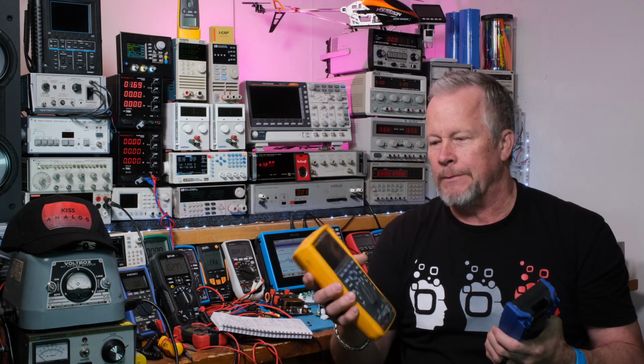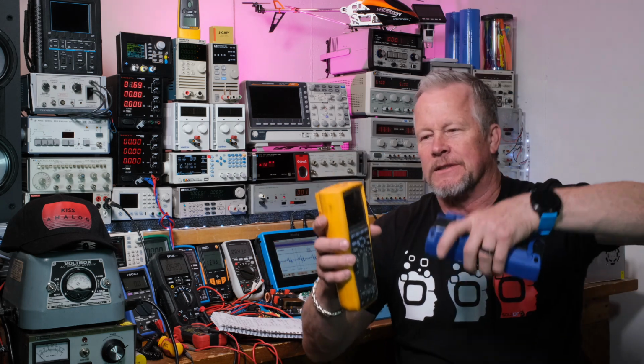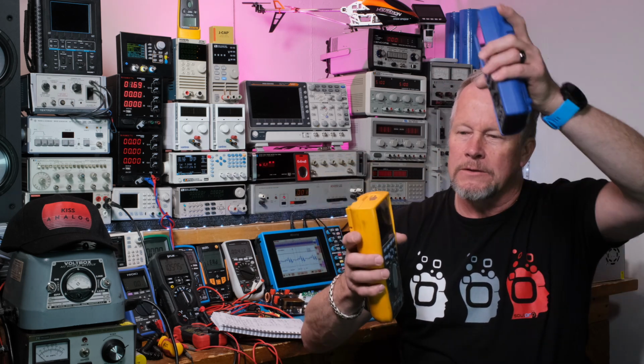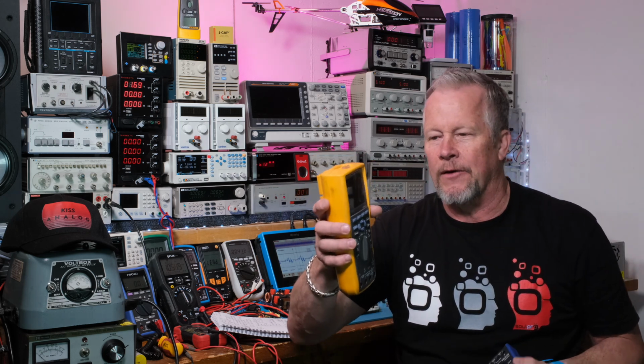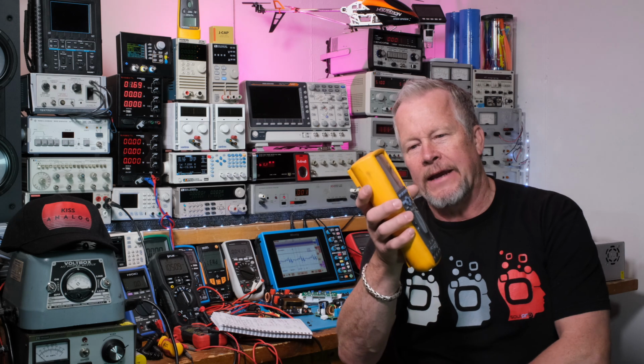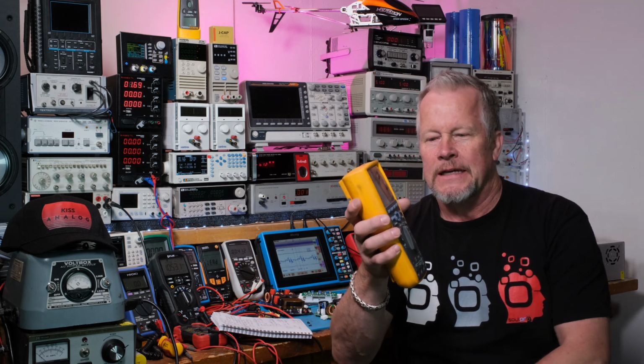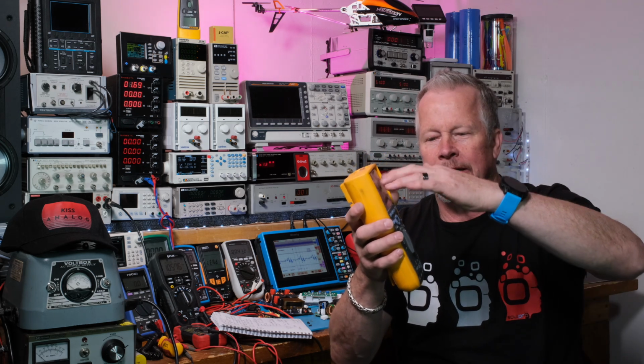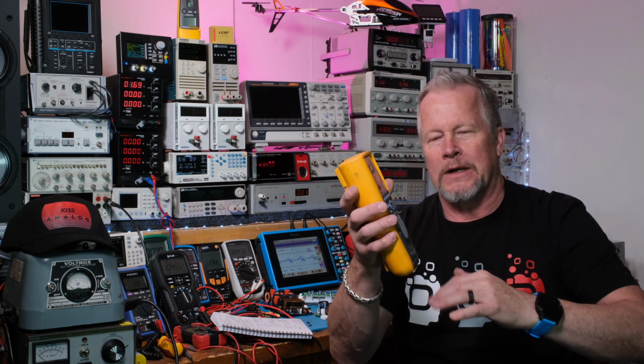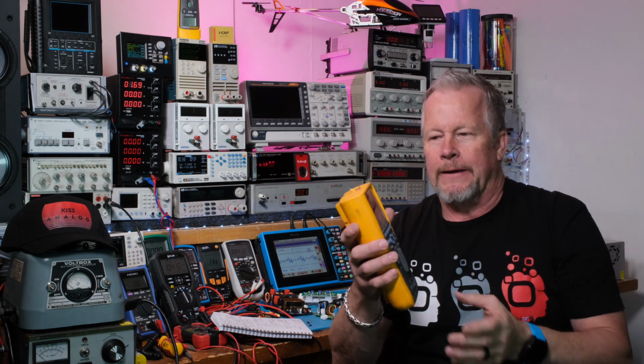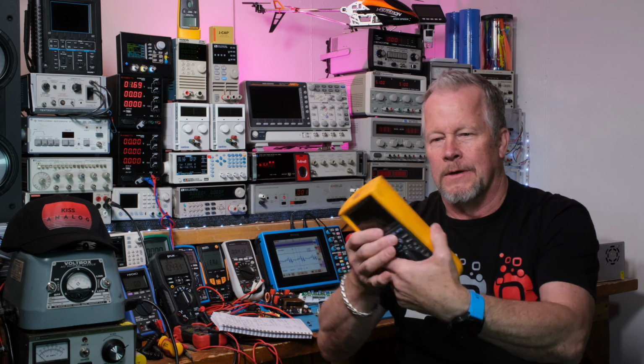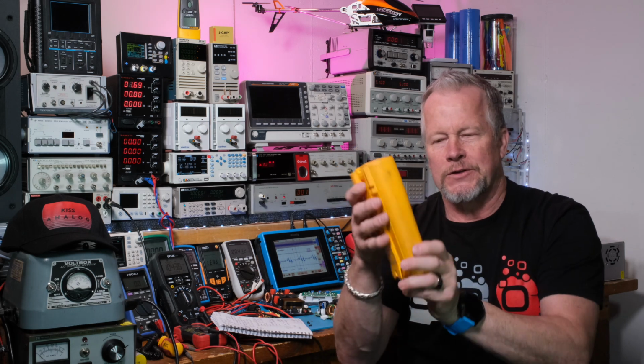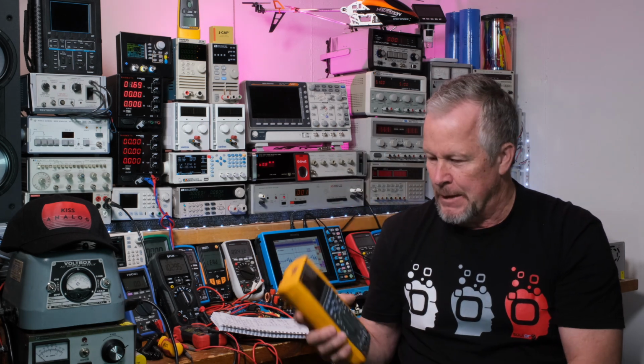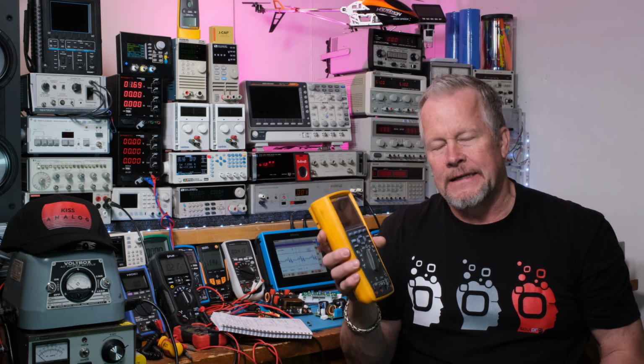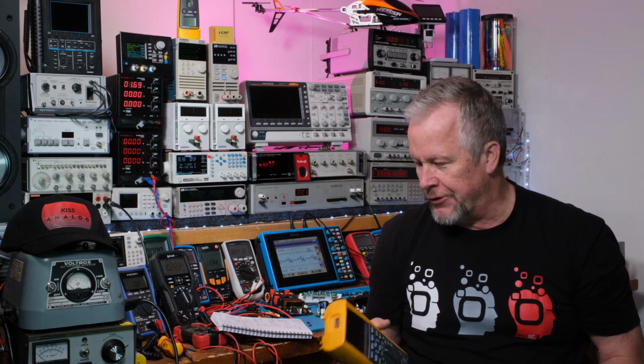Okay, now the 2 means droplets, like not a heavy rain, but some sprinkles coming down, and you turn the angle, I think it's 15 degrees. So that means water's going to hit it, you're going to get a little bit of water trickling down, and it's going to be okay. I think they do it on each surface, okay? 15 degrees. So that is the 42.